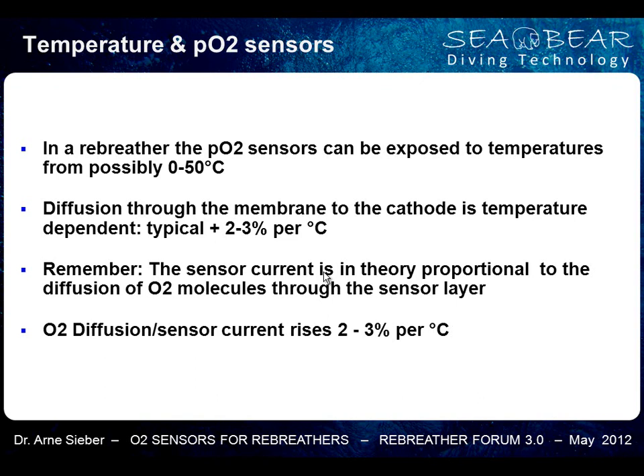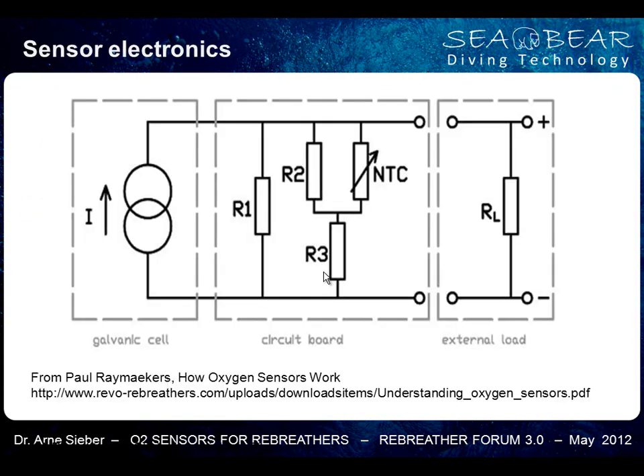This is typically something like 2 to 3% per degree centigrade. The sensor current is in theory proportional to the diffusion of oxygen molecules through this sensor layer, which means the oxygen diffusion and also the sensor current rises by 2 to 3% per degree centigrade. So here's a nice picture from Paul's excellent article about oxygen sensors.